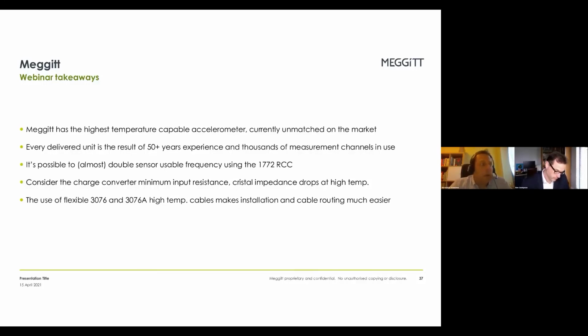Using our unit and our RCC, it's almost possible to double the available bandwidth of a measurement channel. We have to consider all the time when we are working in high temperature environment, probably the audience knows better than me, the change in inner impedance or the inner resistance of the measurement chain. That is always occurring because the crystal impedance is dropping at high temperature. Then the use of flexible cables, so our 3076 and 3076A, is making installations much easier, cable routing comfortable, and engineer's life easier, I would say.